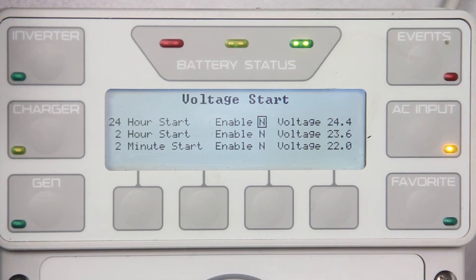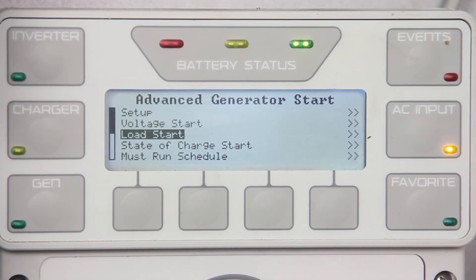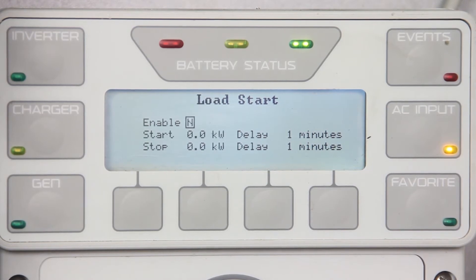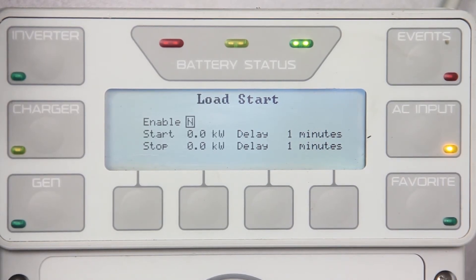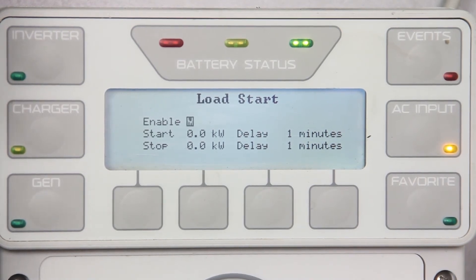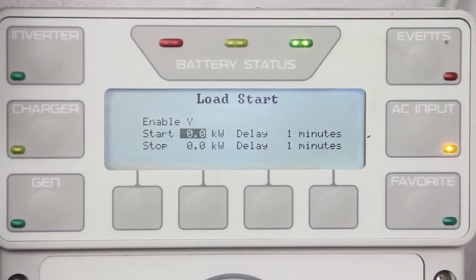Press up once and scroll down to load start. Load start will start the generator whenever the total AC load wattage exceeds the start set point for the programmed amount of delay time. The generator will stop when the AC load has dropped below a stop set point for the amount of delay time. When the generator is running because of this condition, the inverter charger will charge the battery. However, unlike voltage start, it will not perform a full charge cycle. To enable, change the N to Y and enter the desired start/stop condition and delays.